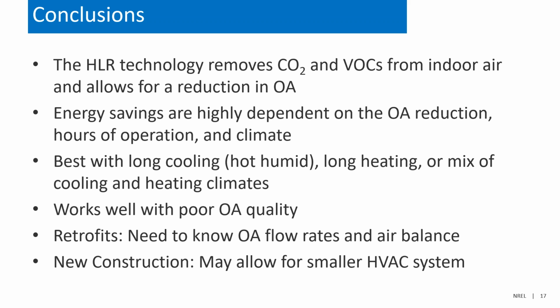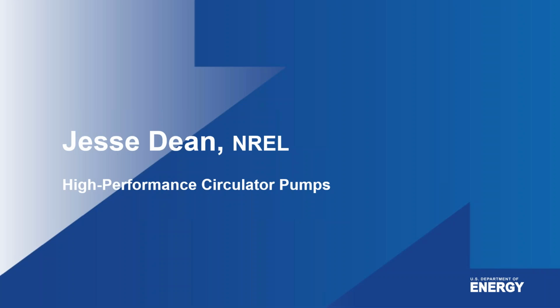In new construction, now you have the opportunity to design this into your system and design the space for it and your ventilation airflow rates and everything. And potentially you may be able to reduce your HVAC system and actually reduce your overall HVAC costs, because now your load is reduced because your outside air ventilation requirements are reduced. All right, so let's move on. And Jesse Dean's going to talk about high performance circulator pump testing that we did.